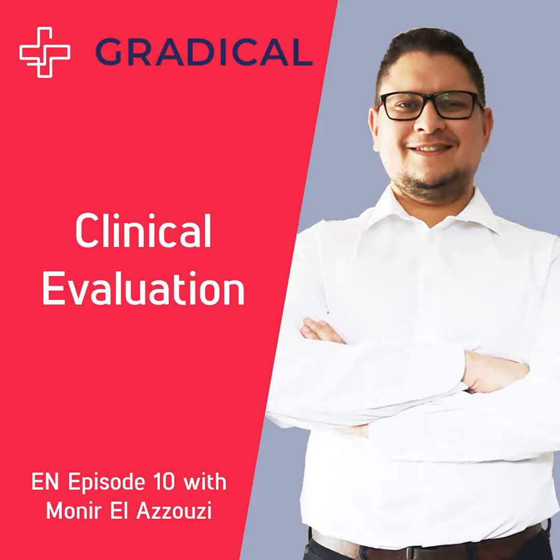Second is biological. This is where it can be a problem for your equivalent device, because biologically the question is: is it using the same material? Does it have the same interaction with the body? Does it have the same biocompatibility aspects, etc.? So on the biological aspect, as it's a different material, there is a difference. Now, can you justify that this difference of material is not significant?